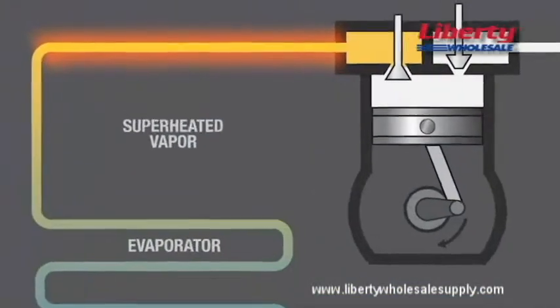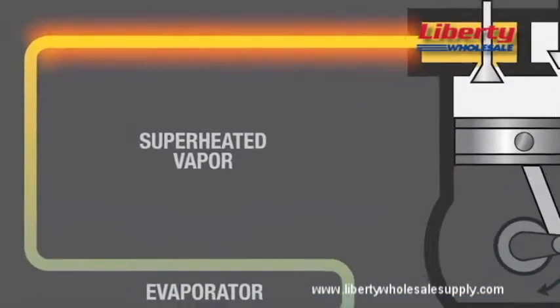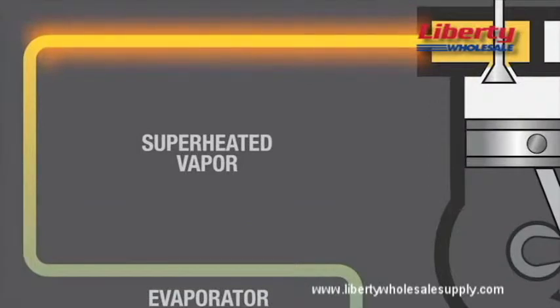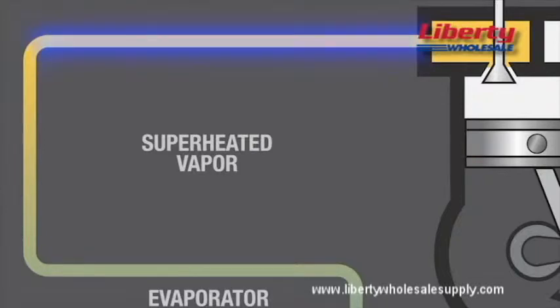If superheat is too high, then not enough refrigerant is flowing to the evaporator, resulting in poor refrigeration and excess energy use. If the superheat is too low, then too much refrigerant is flowing to the evaporator, meaning liquid is getting back to the compressor and causing damage.